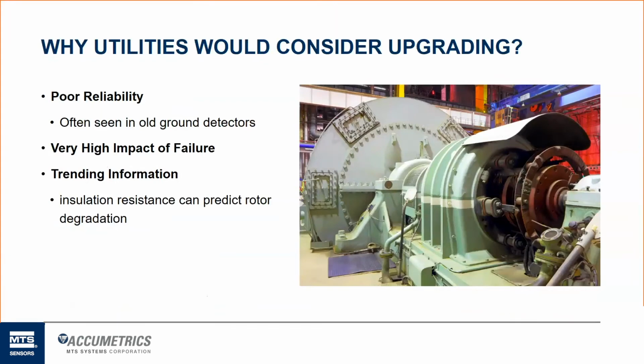So what a lot of utilities will do in that case is they'll schedule sort of unnecessary outages just to check and make sure they don't have a ground fault and turn the unit off. And when you're off and not creating energy, you're losing money, and that's something that they don't like. So our trending information and our ability to more accurately measure the field resistance gives them that peace of mind that they're going to be monitored much more accurately than traditional systems that are out there.